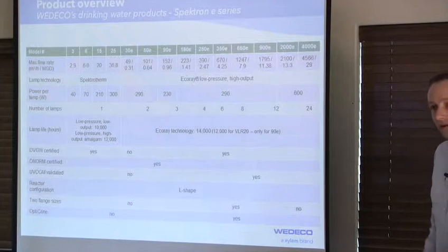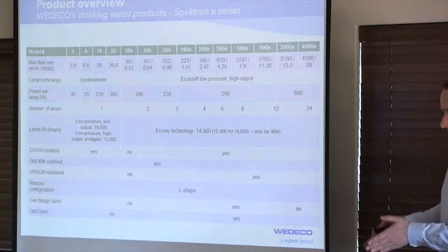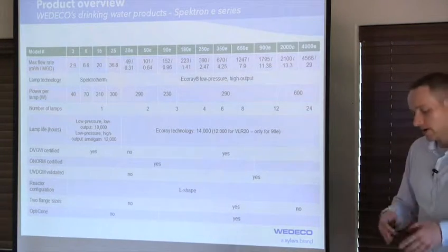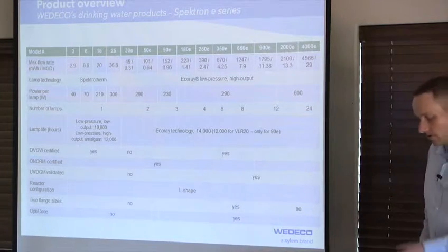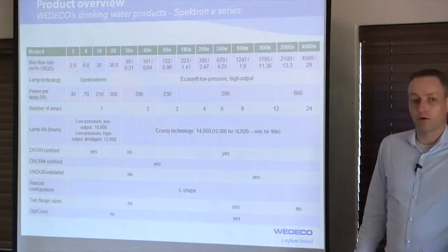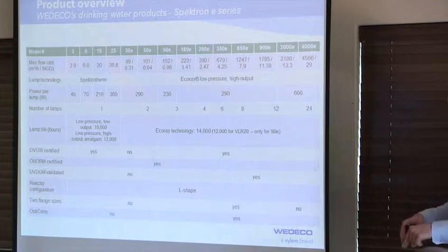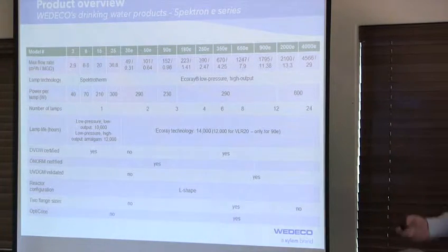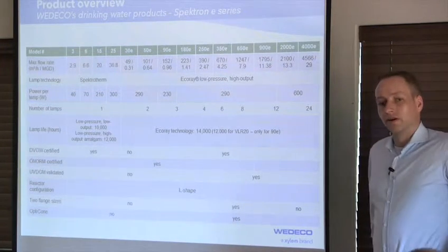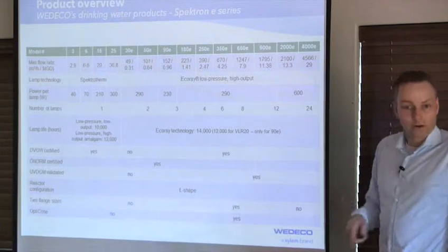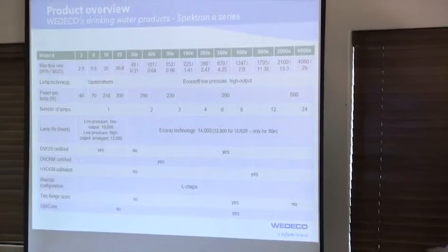UVDGM is done by a third party, and with these reports you can then select a system and design it target specific to one special pathogen. If you know, okay, I've got a Legionella problem, then you can design your UV system to fit directly this application, to design it specifically for Legionella, 2-log, 3-log Legionella reduction, for example. So it acts as more of a process guarantee?